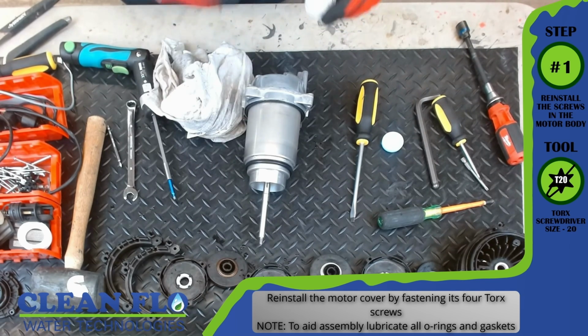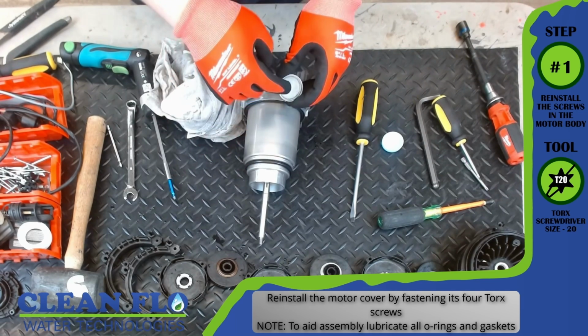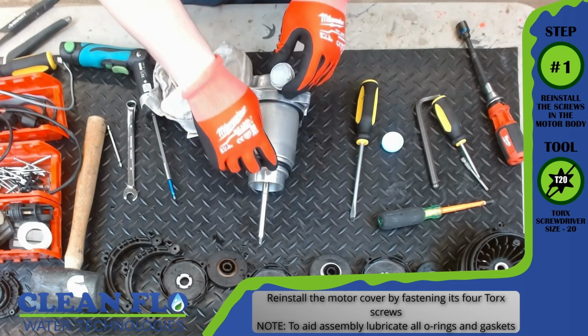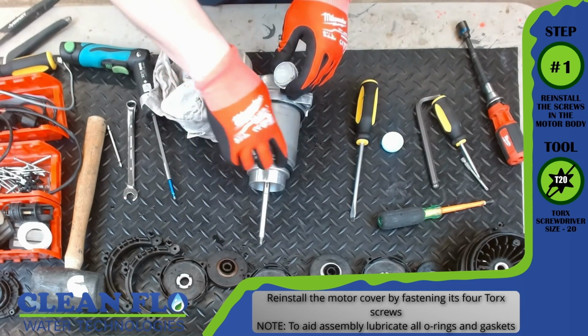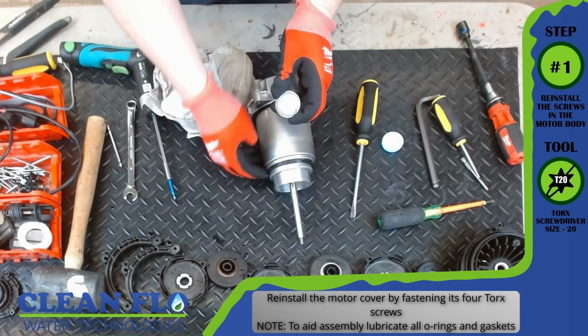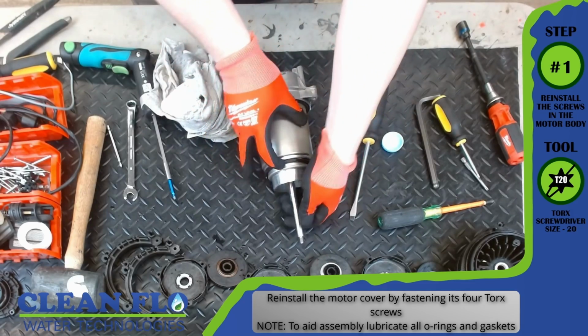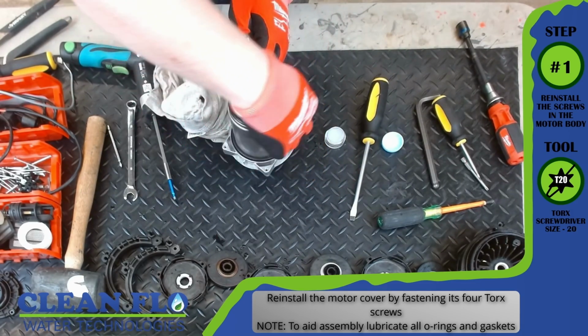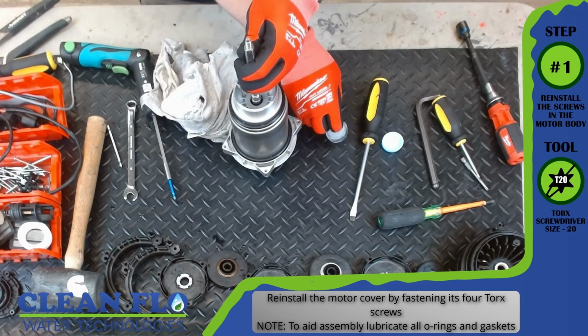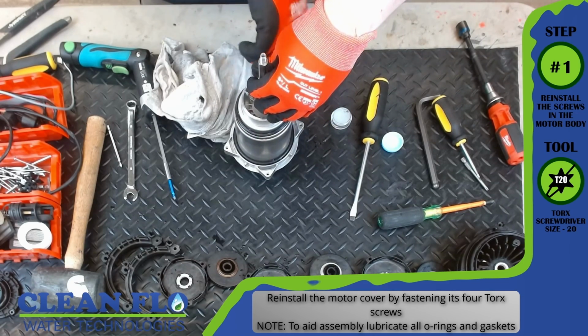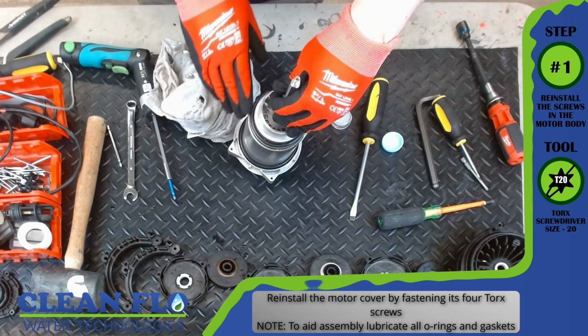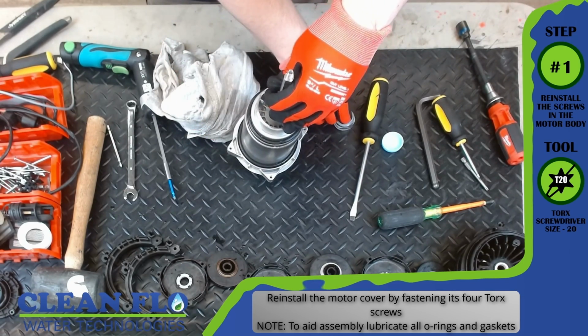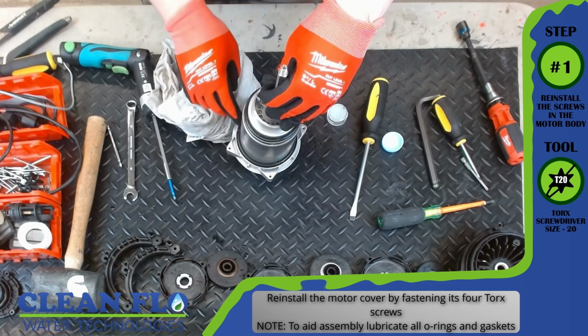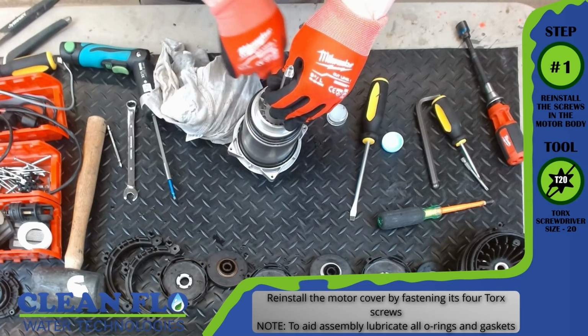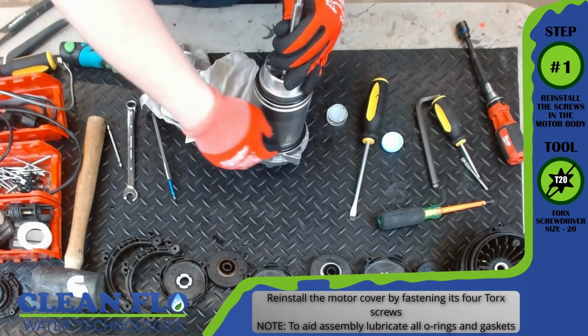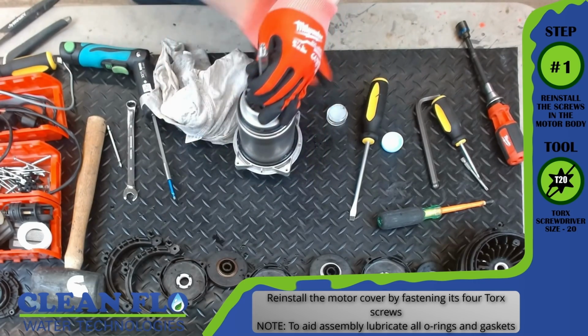Be sure to always be using silicone when reassembling the Esybox pump or any pumps with O-rings. The silicone will provide the necessary lubricant for the O-rings to slip into place properly without pinching them. Failure to use the silicone lubricant can result in pinched O-rings, unseated O-rings, and possibly having to rebuild aspects of the pump once a leak is found.